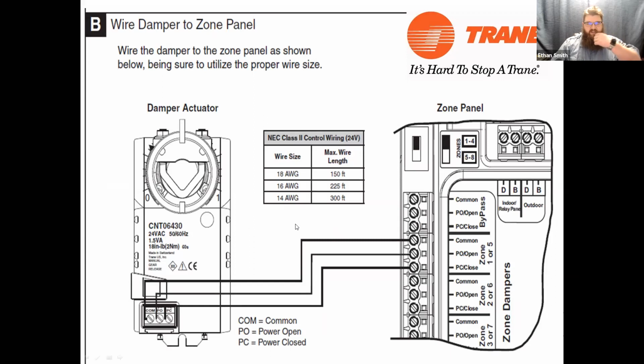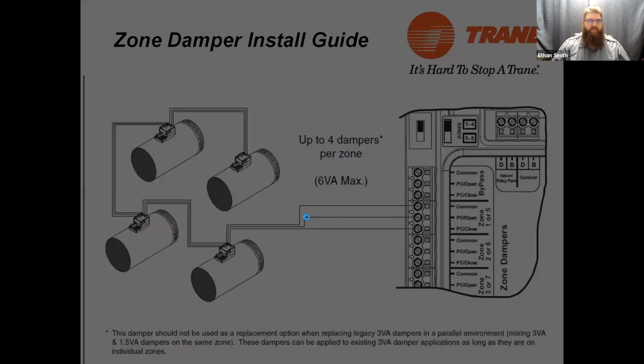There's just a picture of that damper being wired up. If you're using 16 gauge wire, the longest you can run is 150 feet. Then we start to get signal degradation. If you want to go further than that, we're going to start talking about 16 or 14 gauge wire. I've never run into a system that's got a damper 300 feet of wire away from the zoning, the furnace. So usually they're pretty close.